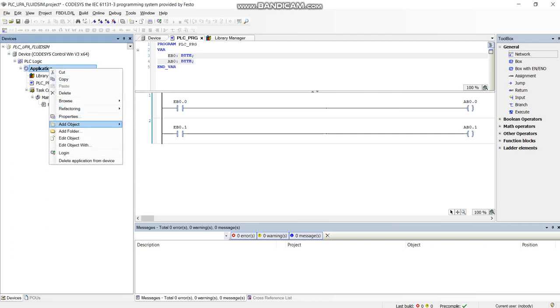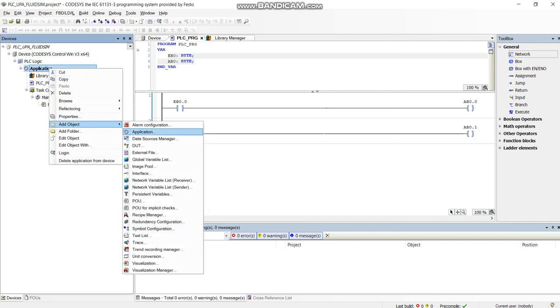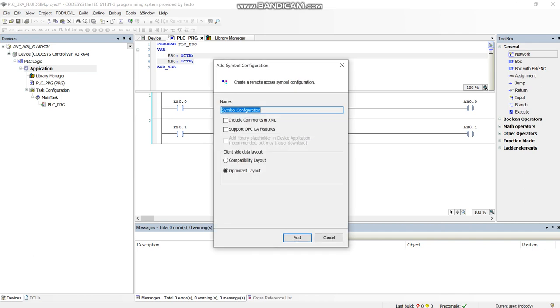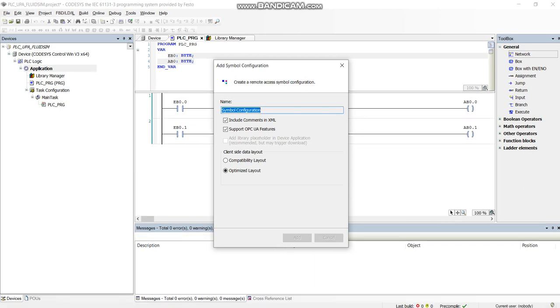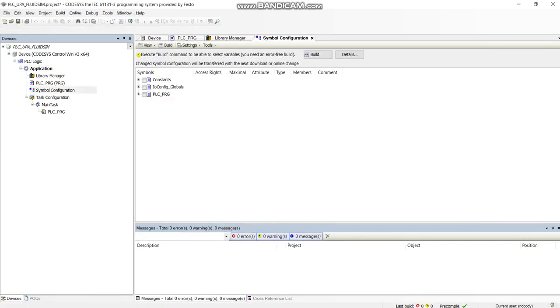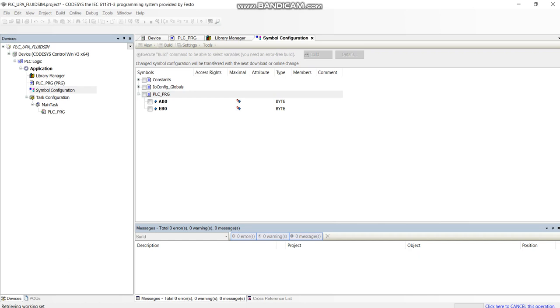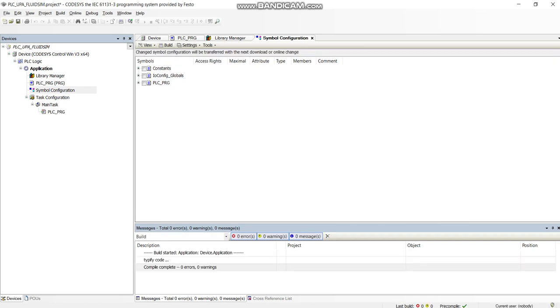All you got to do is add it in from application, add object, symbol configuration, and tick the boxes. Make sure you tick OPC UA features and add that in. What this does - if you perform a build first, you'll be able to tick what you want to bring across on the OPC. So we'll do build first. You'll see I'll be able to tick those and that's what will be transferred across - those two byte information from the PLC program.